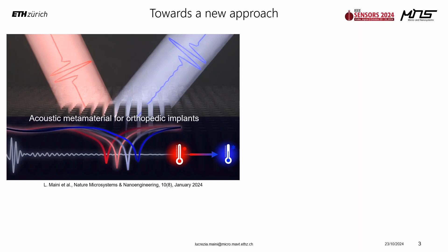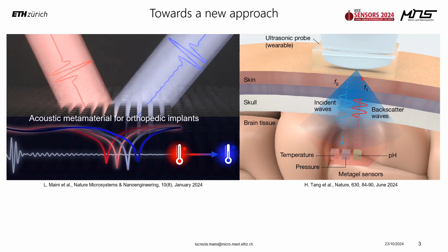This is a very new approach, which has also started to be explored by other groups, such as in this case, where they have developed this metagel sensor to monitor temperature, pressure, and pH in the brain using ultrasound waves. Now, the advantages of using ultrasound waves are mostly two. The first one is that for the same penetration depth we can introduce much lower power levels in the body, up to 72 times less, which means that this approach is safer for long-term interrogation in the patient.